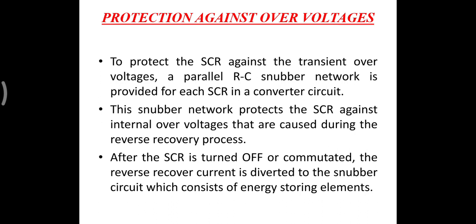To protect the SCR against over voltages or transient voltages, a parallel RC circuit is connected across the SCR. So by using the RC snubber circuit, we can protect the SCR from the transient over voltages.